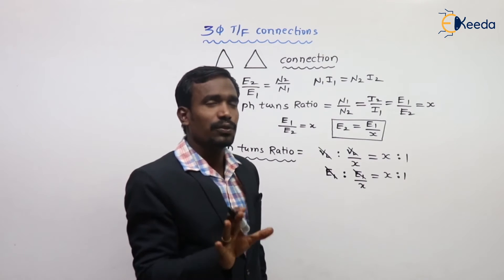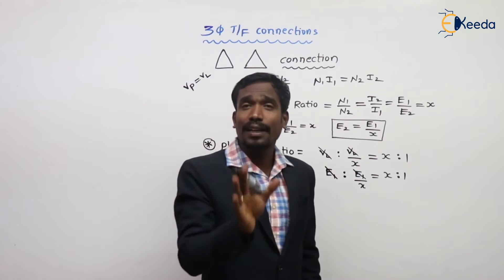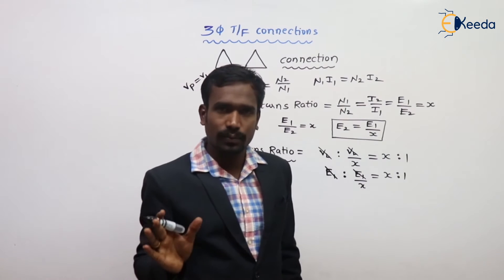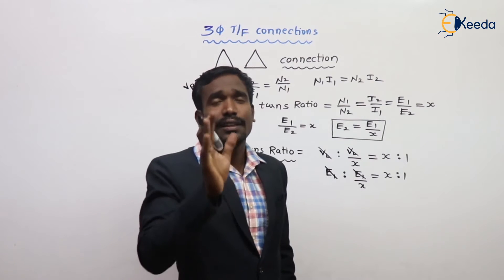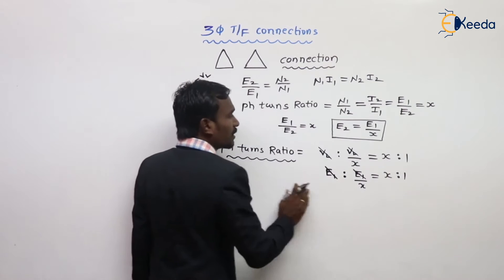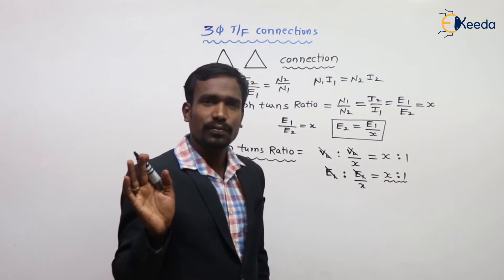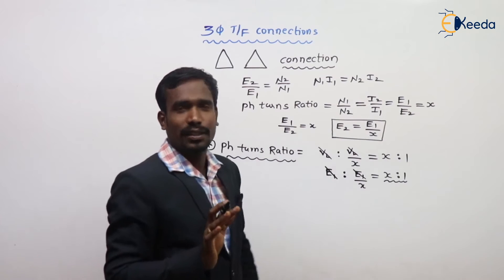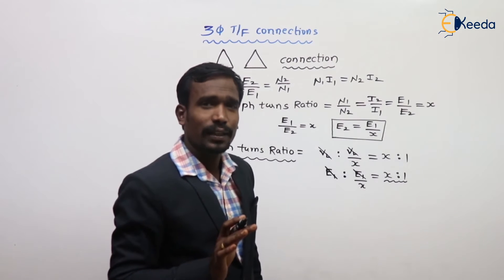Once a transformer is manufactured, the phase turns ratio is constant. But the line turns ratio changes for every configuration. For different connections, the line turns ratios change, but the phase turns ratio is constant for all configurations and all connections.